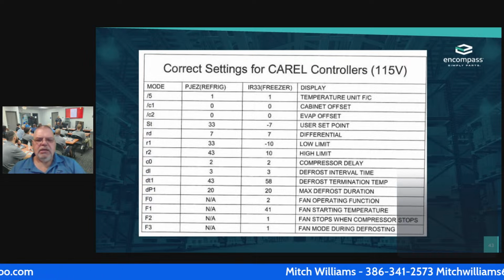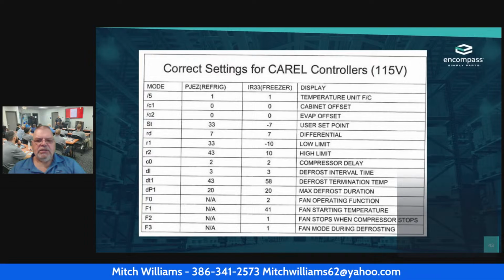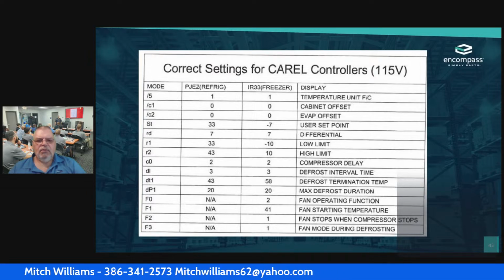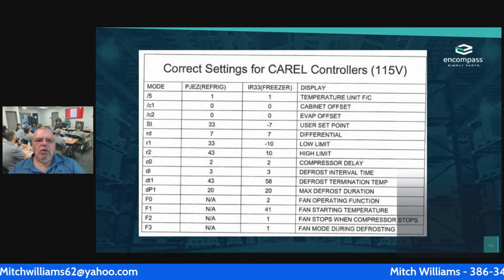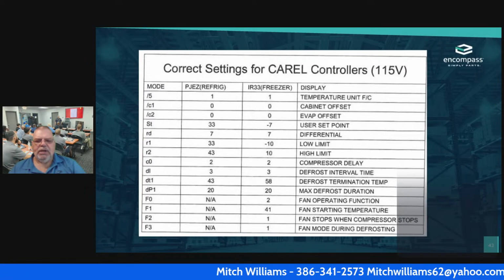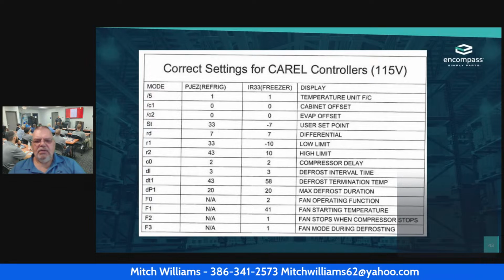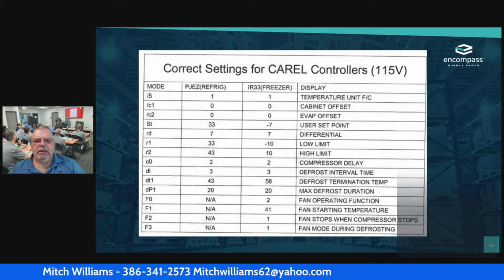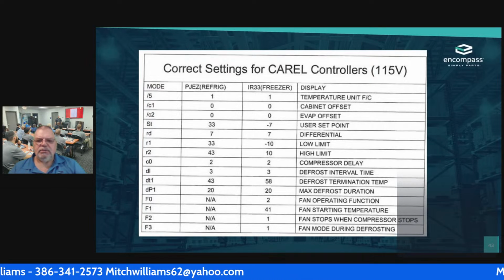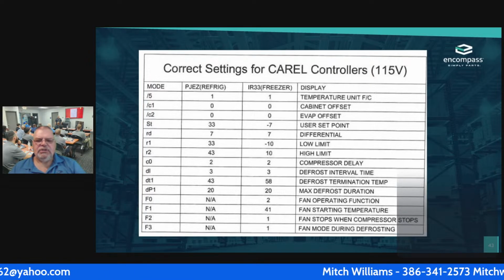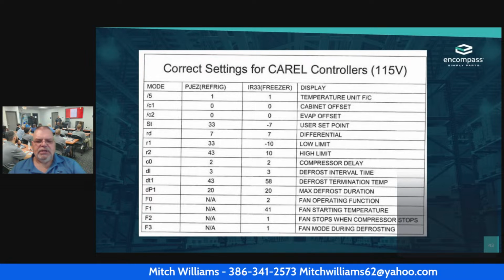Our RD is 7 and 7 on both. R1 is 33 for the refrigerator, -10 for the freezer. R2 is 43. So you have a 10-degree swing there. And then we have a -10 and a 10 for the freezer section. That's the low limit and the high limit. Then for the C0, the compressor delay, they're both set at 2. Please don't change those.